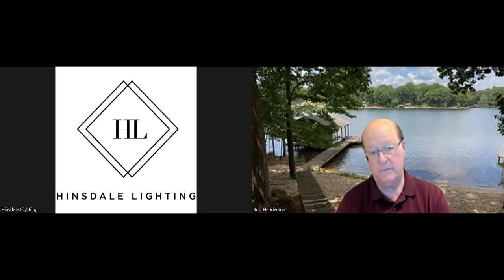So what you have to do, you have your particular lamp that you want to try, or a particular fixture with a certain center beam candle power. That's given, right? So then you say, what is my distance from that fixture, wherever it's mounted? It could be mounted on the ceiling or wherever, because you've got different pitches depending on what you're using. What is the distance from there to the object that you're lighting? And I'm assuming that's an item on a vertical wall. Is that correct?